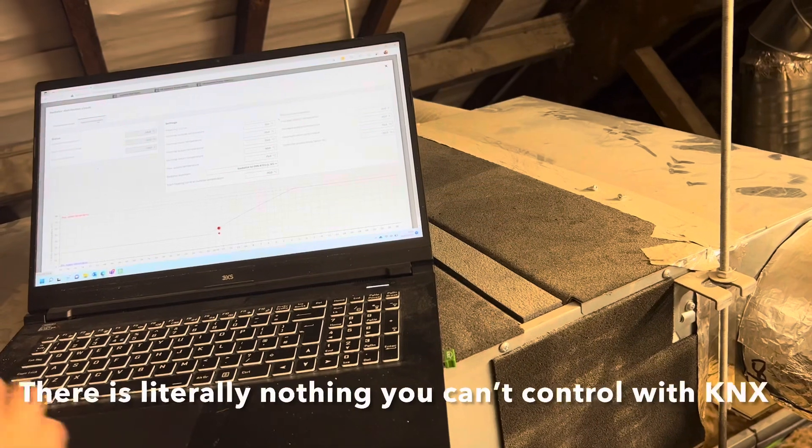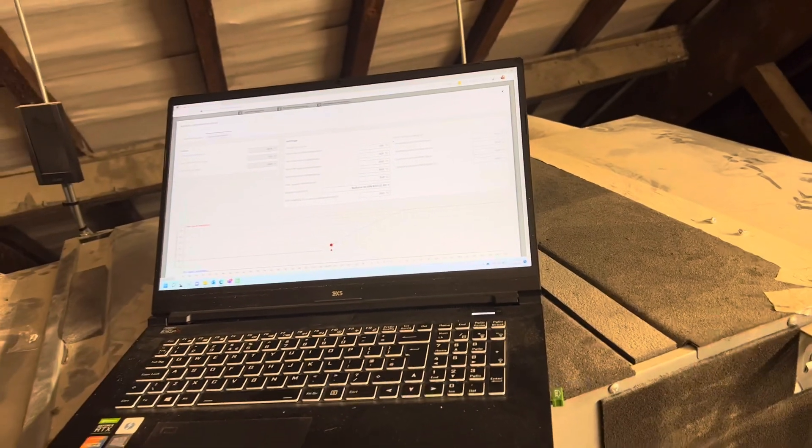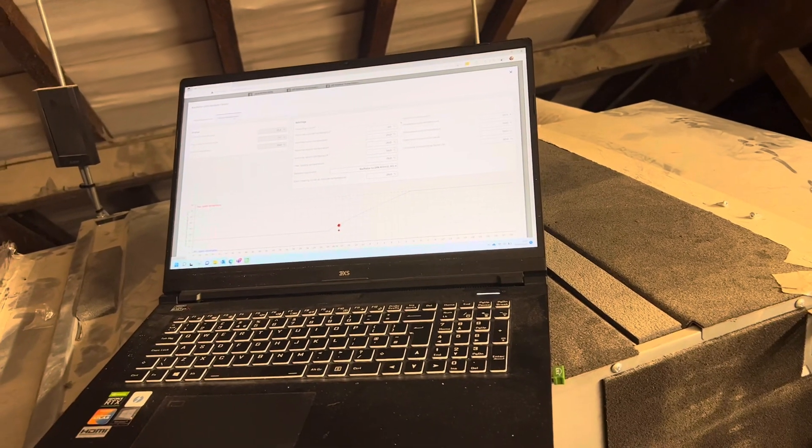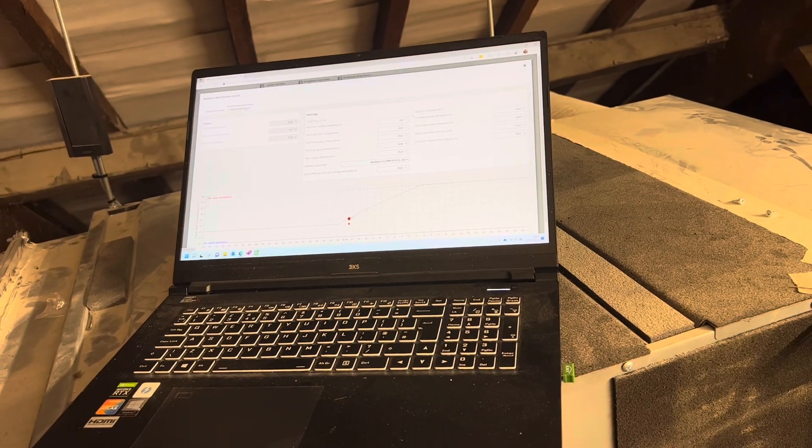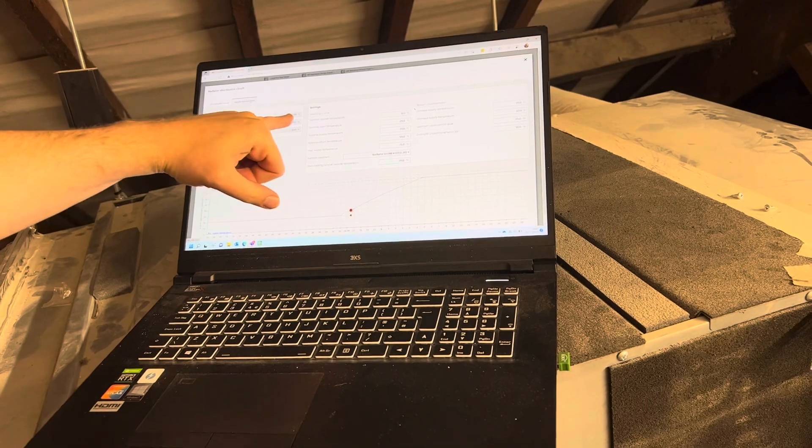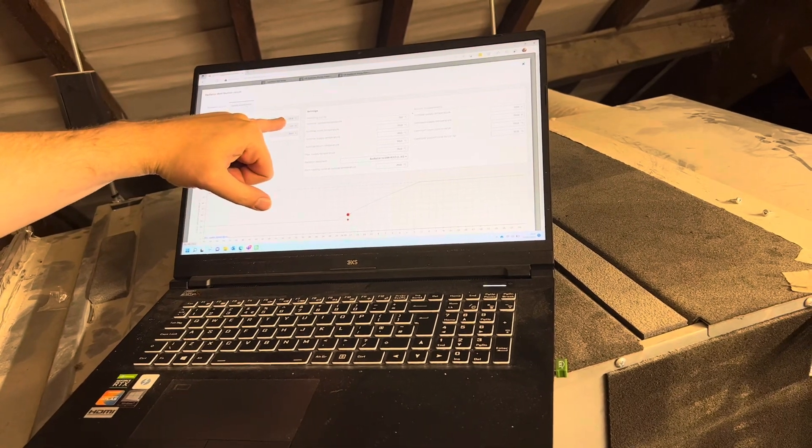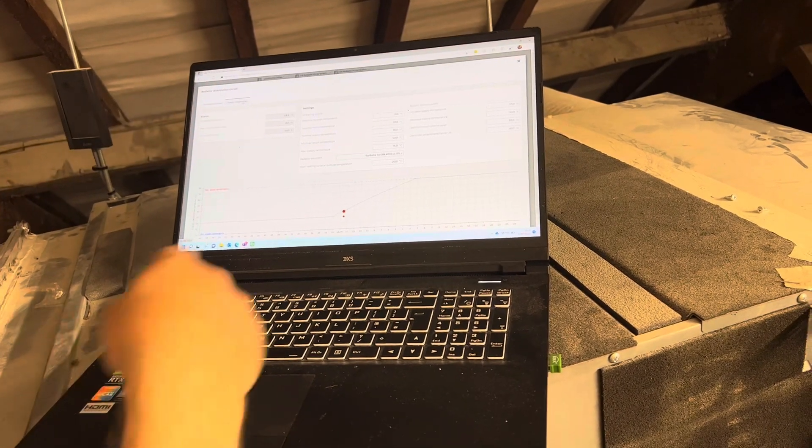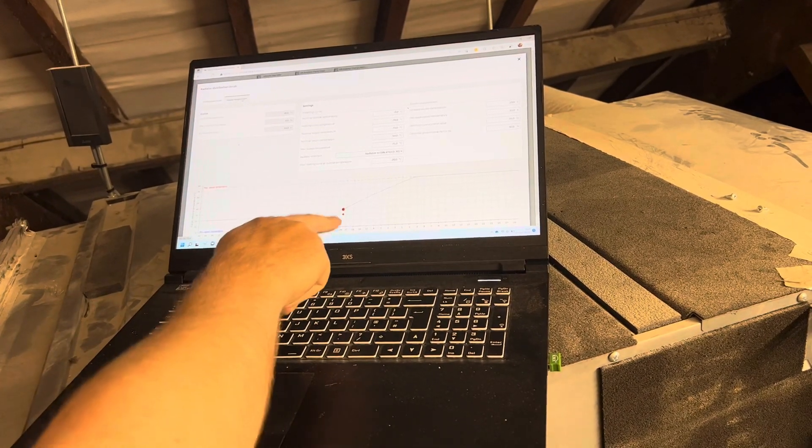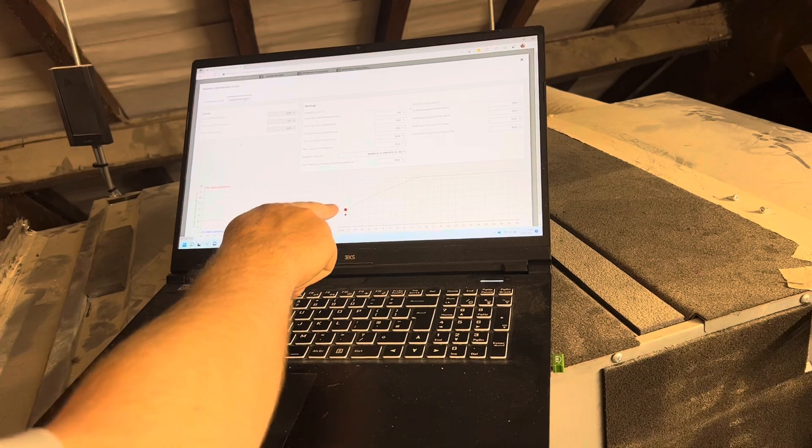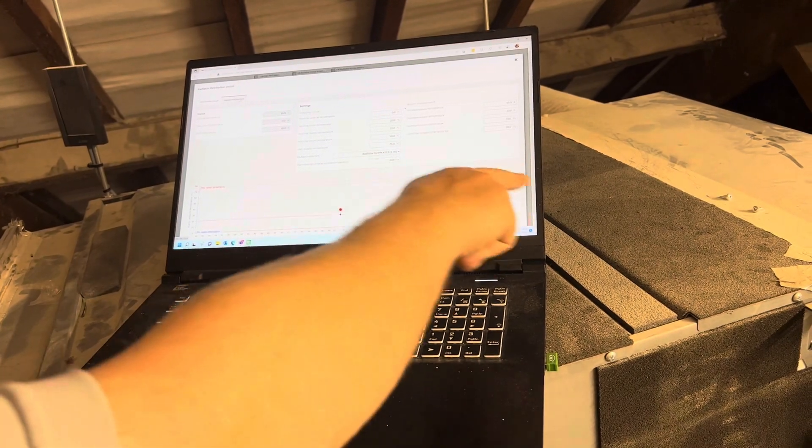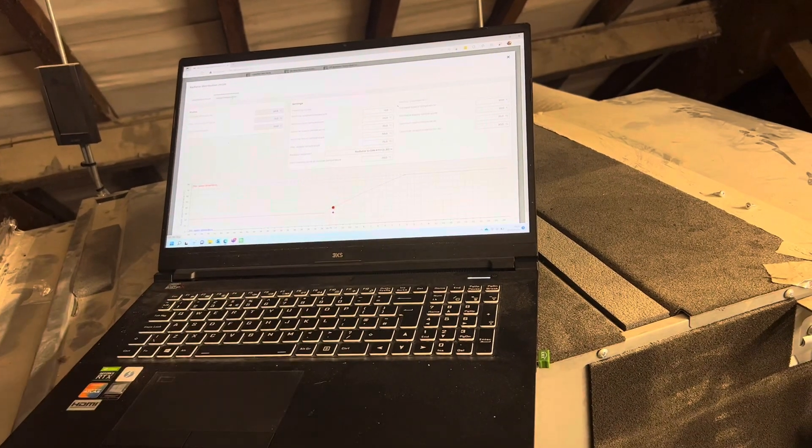And then you've got weather compensation on there. So that's the outside temperature, it's 18.8 degrees outside, and you can see that it's using this weather curve, a compensation curve, to set the temperature.